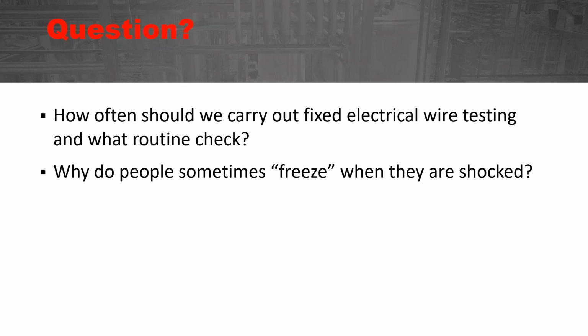So if you're utilizing the equipment at 90-95% capacity versus utilizing it at 30% capacity, there's a lot of extra heat when you talk about current going through it, and that may negatively impact the wire insulation and reduce the expected life much more than it would at 30%. So I think checking it a little more frequently in the 90% scenario would make sense versus checking it at 30%. So that's something just to keep in mind. There's not one specific fixed answer for that question.